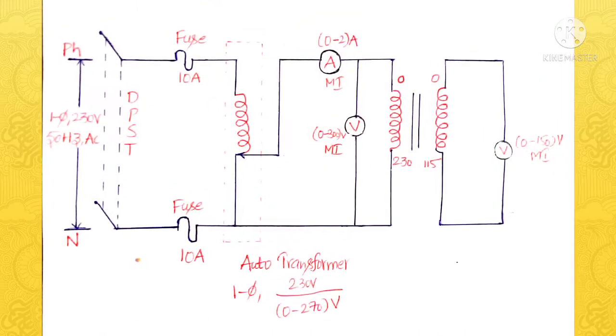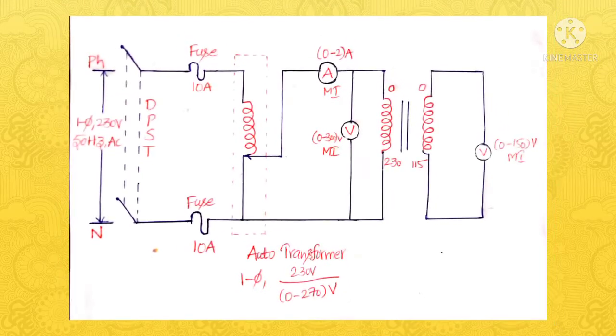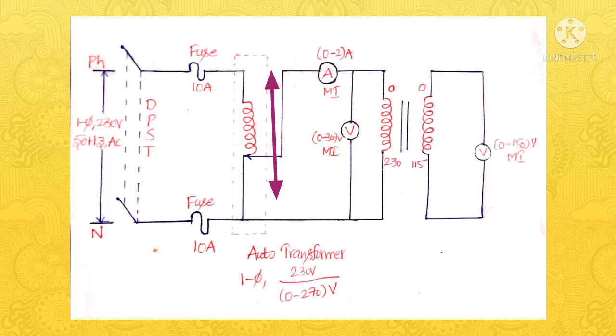This experiment is conducted in two steps. In the first step, we will connect the circuit as shown in the diagram. Here we have an autotransformer as well as a transformer. As the first step of the experiment, by keeping the autotransformer in the minimum position, we will close the DPST switch. After closing this, by varying the autotransformer, we can vary the voltage supplied to the primary, the voltage supplied to the secondary, as well as the current drawn by the primary. We will note down all these parameters.